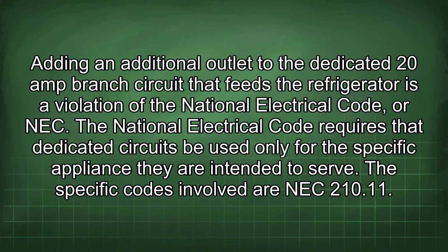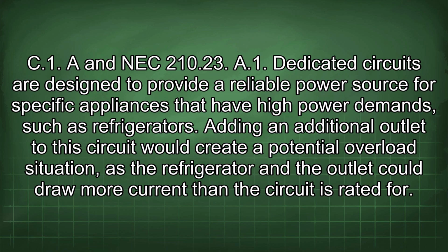Adding an additional outlet to the dedicated 20-amp branch circuit that feeds the refrigerator is a violation of the National Electrical Code, or NEC. The National Electrical Code requires that dedicated circuits be used only for the specific appliance they are intended to serve. The specific codes involved are NEC 210.11, C1, and NEC 210.23, A1.